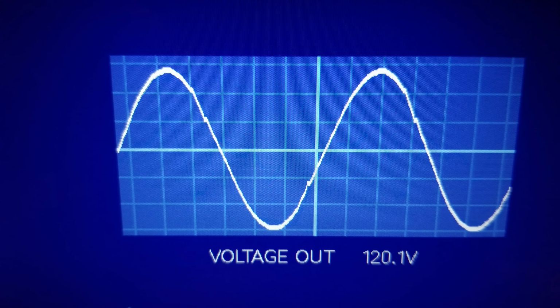Here we're looking at the sine wave on the output side of the regenerator, and as you can see, the top and bottom peaks have been smoothed out quite a bit, and the harmonic distortion, as we measured before with the Fluke meter, has been significantly reduced. Now you do have the option in the regenerator to have it concentrate on keeping an accurate output voltage of 120 volts, or whatever your mains is configured for, or you can have it concentrate on reducing the harmonics as much as possible and allow the voltage to deviate a little bit from nominal. The choice is up to you, but right now I have this regenerator configured for maintaining the output voltage to a tight tolerance and allowing the harmonics to drift around a little bit, which isn't much. I've seen it go from 1.2% down to 0.7 up to about 1.7%.